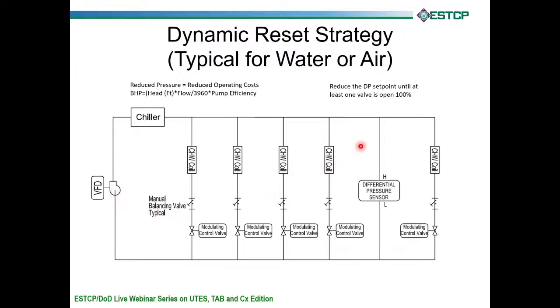So what the control contractor can do is reset the differential pressure set point. We pretended it was 10 psi. He can reset it down to 9 and then wait and see what happens. So he resets it at 9. The pump slows down. We've got less water flow now. Eventually, these valves will start to open up because the space may be getting hot because it's getting less water. And you want to keep resetting that set point down until at least one of these valves is fully open.